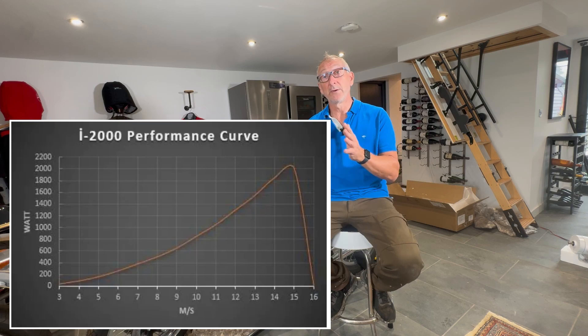The ratio of power is not linear to wind speed — doubling the wind speed will give you an eightfold increase in power. So with wind turbines, the higher the wind speed, the greater the multiple of output power you'll get. It's really important to know that wind turbines can look like they're running — they're turning around and can often look quite fast — but they're not really producing anything.